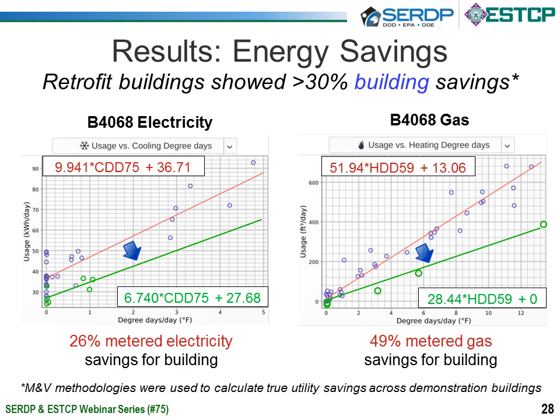So one of the results here, this is the results from 4068, which was one of the smaller buildings there. We use full M&V methodologies that ESCOs would use to show the actual measured daily energy savings here. And our results were quite good. We saw 26% metered electricity savings for the entire building. So this is not just the HVAC usage, this is the entire building, capturing lighting and all the other effects there. And on the gas side, we saw almost half the gas savings from these modern controls.